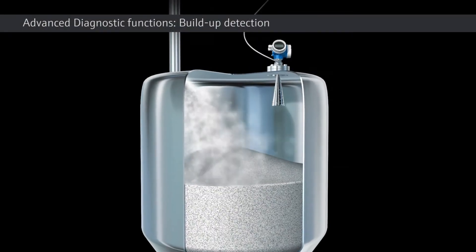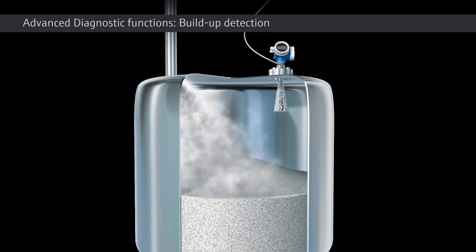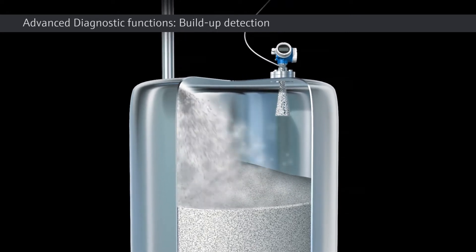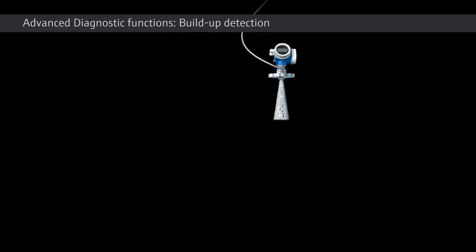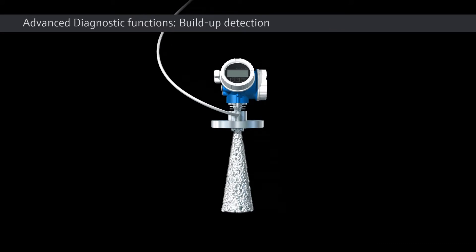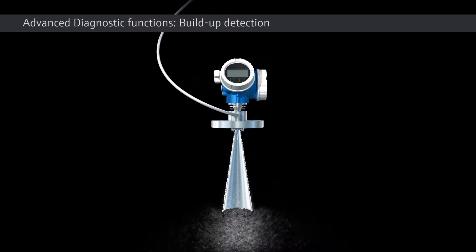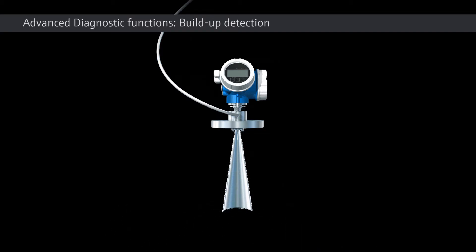Buildup can form on the antenna of level instruments in applications involving bulk solids. These deposits may lead to incorrect measured values, thus exact measurements are not possible. Regular cleaning of the antenna in fixed intervals will ensure reliable measured values, even in the presence of buildup the measurement is working.